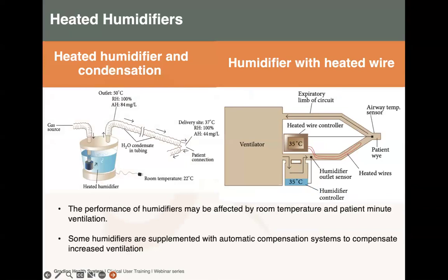Also, the heated humidifiers: some have heated wires and others have a heated humidifier with condensation. I'll speak more on the humidifiers with heated wire. Most of the practitioners here, the anesthesiologists or the critical care physicians, prefer the humidifiers with heated wires, especially for pediatric patients, because they provide enough temperature in the airway and also prevent hypothermia. They work better than the ones with condensation. The performance of the humidifiers may be affected by the room temperature and also the patient's minute ventilation, so these humidifiers are supplemented with automatic compensation systems to compensate for the increased ventilation.